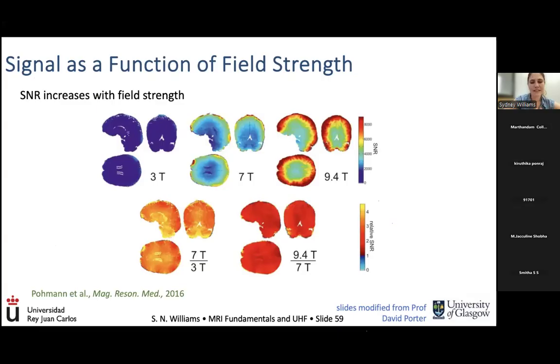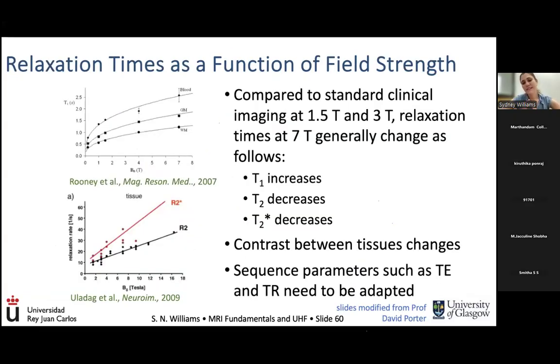Here's a really clear example of why SNR increases. These are showing ratios between 3 Tesla and 7 Tesla, and then 7 Tesla and 9.4. You really see, especially in the peripheral part of the brain in these figures, that the SNR skyrockets at higher field strengths. Importantly, the difference between 7 Tesla and 3T is almost a factor of 4 in some areas of the brain in terms of SNR. So it's very impressive. It means you can do much higher resolution imaging, potentially at a lower scan time, but that is slightly affected by the changes in relaxation.